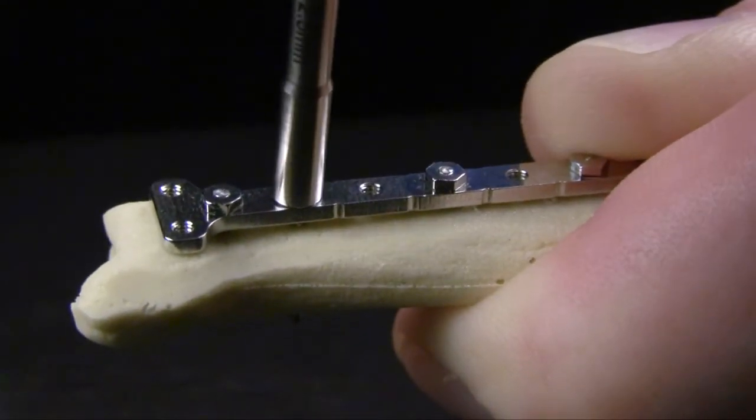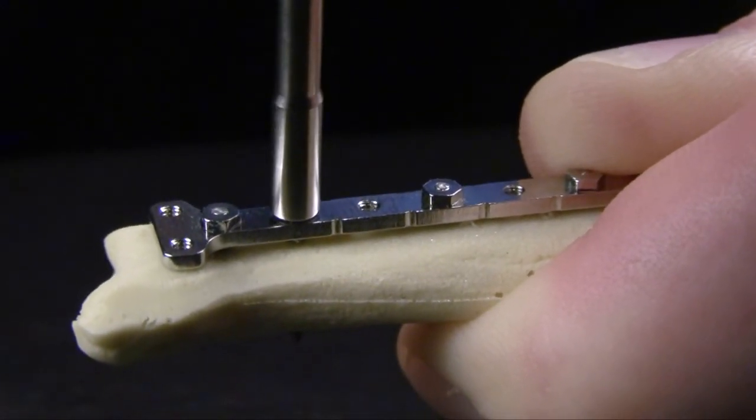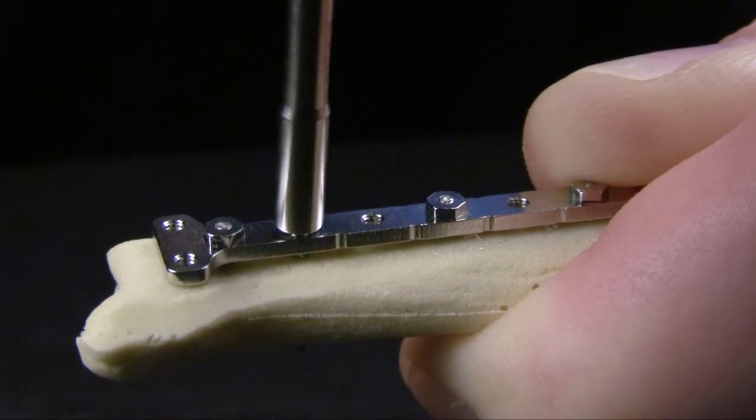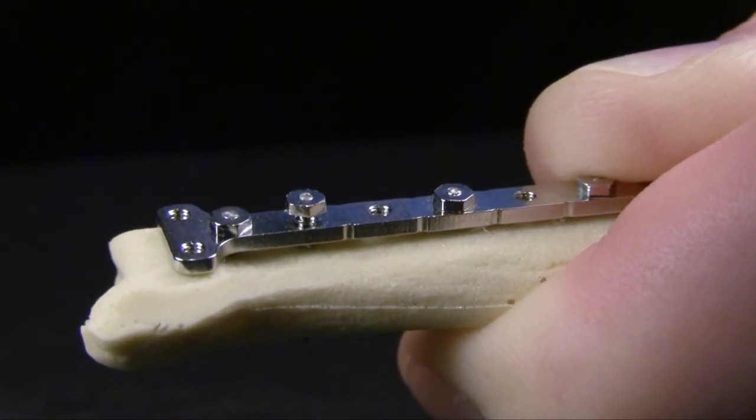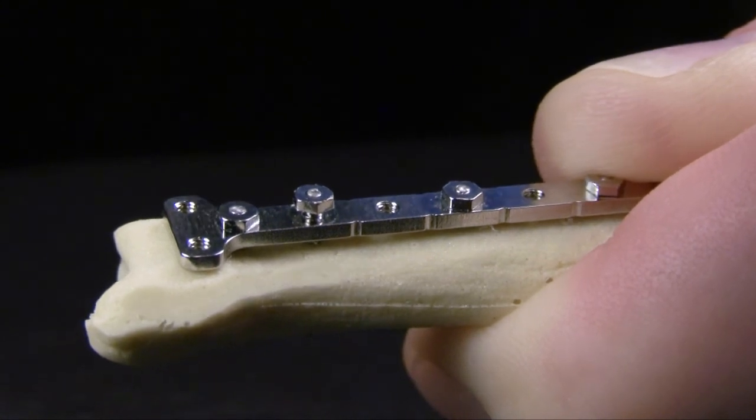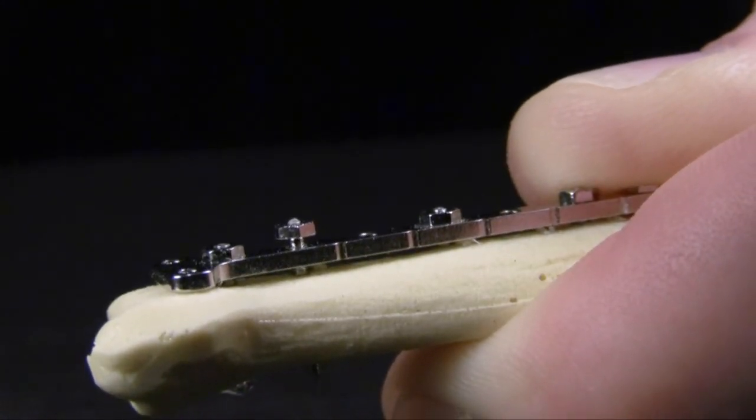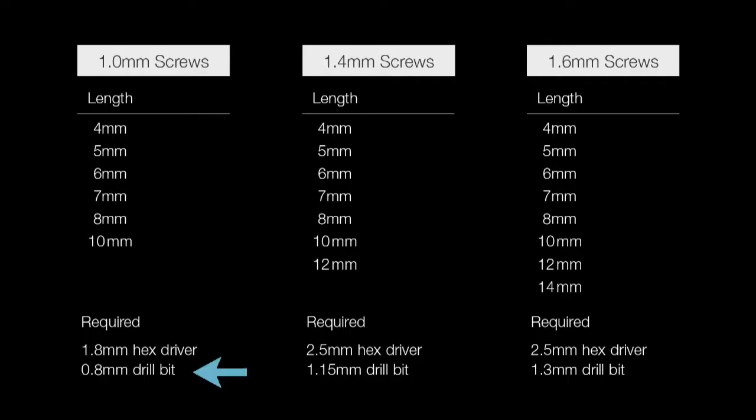Contrasted to very small internal hex or Torx drivers, the external hex head allows the surgeon much more control and mechanical advantage when removing or tightening screws. VetKISS screws are self-tapping but require pre-drilling of the appropriate diameter pilot hole. The 1.0 screw is pre-drilled using a 0.8 millimeter drill bit, the 1.4 screw using a 1.15 millimeter drill bit, and the 1.6 millimeter screw using a 1.3 millimeter drill bit.